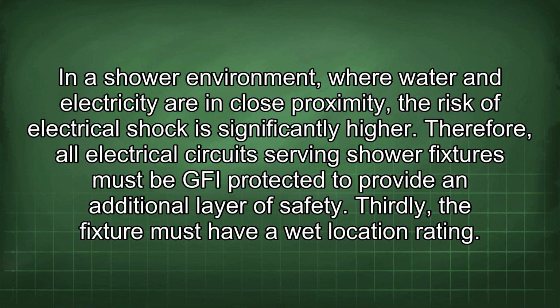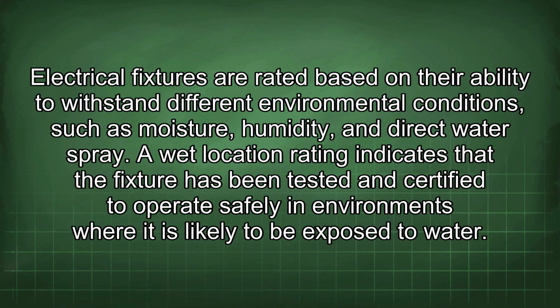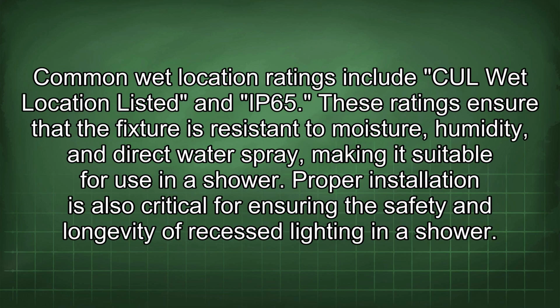Thirdly, the fixture must have a wet location rating. Electrical fixtures are rated based on their ability to withstand different environmental conditions, such as moisture, humidity, and direct water spray. A wet location rating indicates that the fixture has been tested and certified to operate safely in environments where it is likely to be exposed to water. Common wet location ratings include CUL wet location listed and IP65.